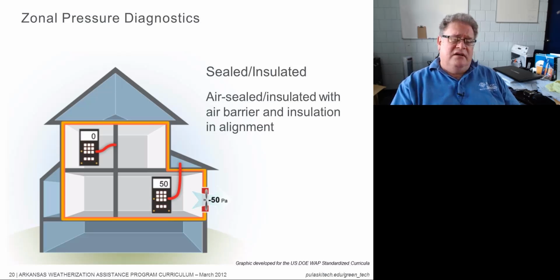But this one up here, upstairs, is showing a 0 Pascal difference. Well, that's what we would expect to see. That's an interior wall. If it has connections from one room to the other through that wall, that's okay. But it should not be being pulled down at all. It should be at the same pressure as the house, whatever the house pressure is.